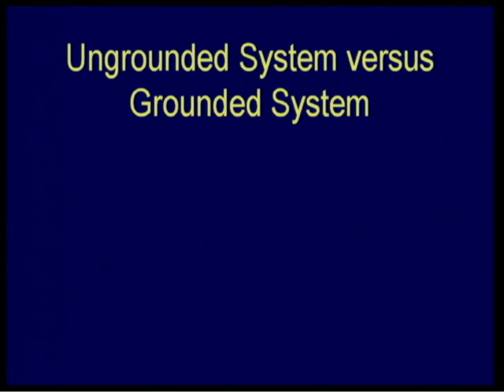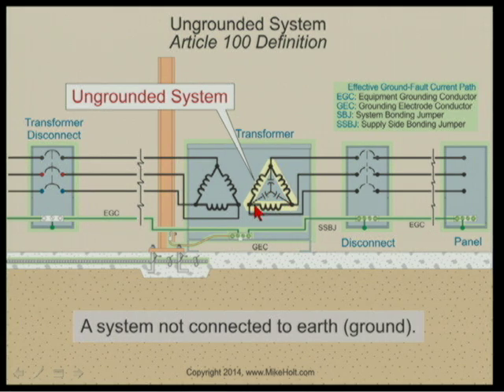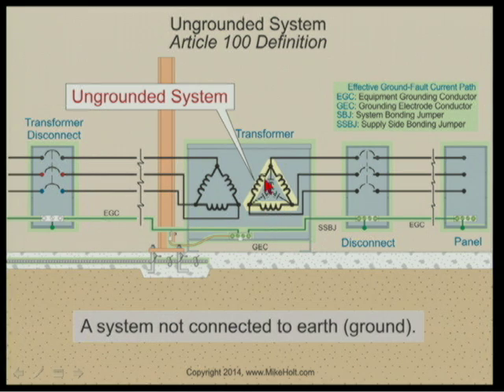There are two types of systems. You have an ungrounded system. Let's take a look at this. Take a look at the secondary winding. You are assumed, taking this course, that you understand electrical theory. This is a system — the secondary is insulated, and these conductors themselves are all insulated, and there is no fault. None of these conductors are connected to any equipment. That means that this system is ungrounded. The actual winding is not connected to anything that could be an extension to the earth — it's not connected to the enclosure that has a connection to a conductor that has a connection to the earth. So therefore that system is not grounded.